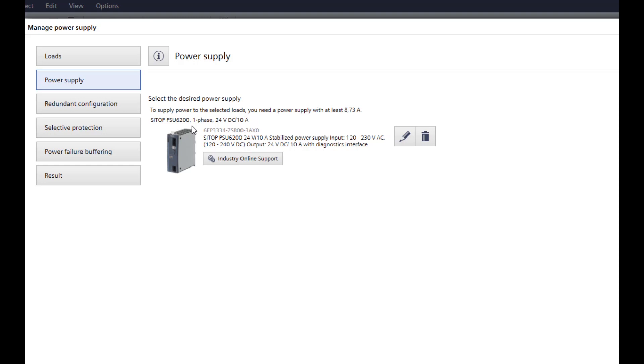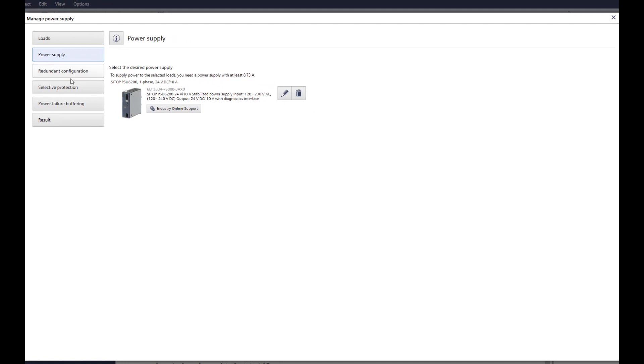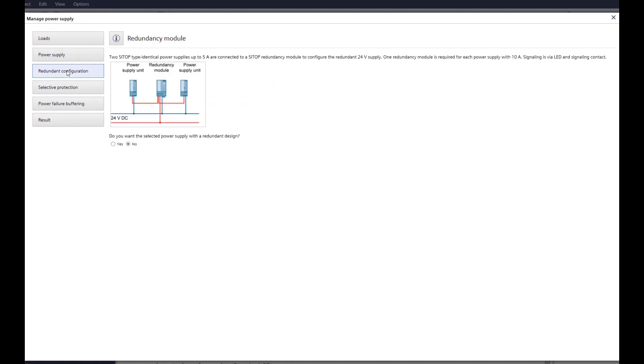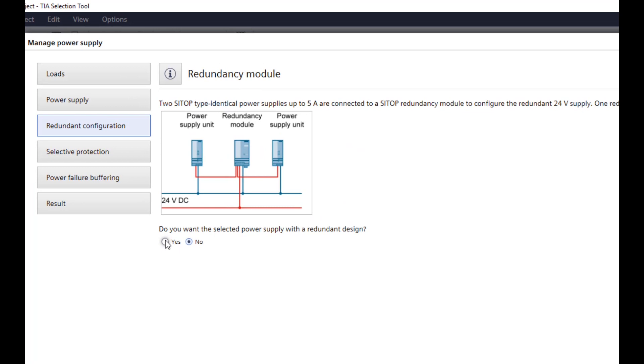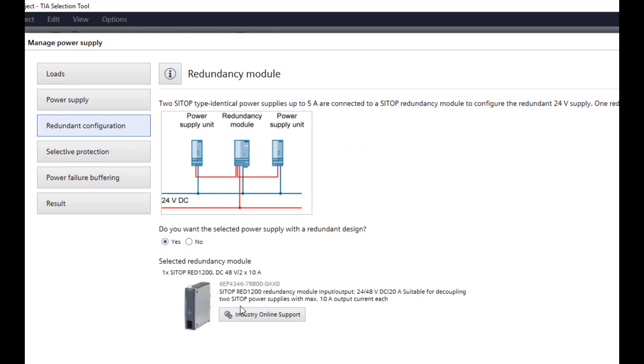A redundancy module and an electronic fuse module should be added to the 24V supply to ensure the availability of the DC power supply in the event of a fault. To select the appropriate RED1200 redundancy module, select redundant configuration on the left side of the wizard. After answering the question about a redundant structure, the redundancy module is displayed, along with important data about the device and a direct link to online support.